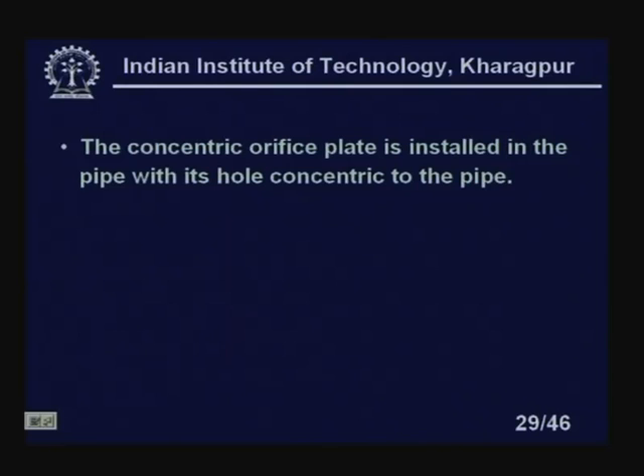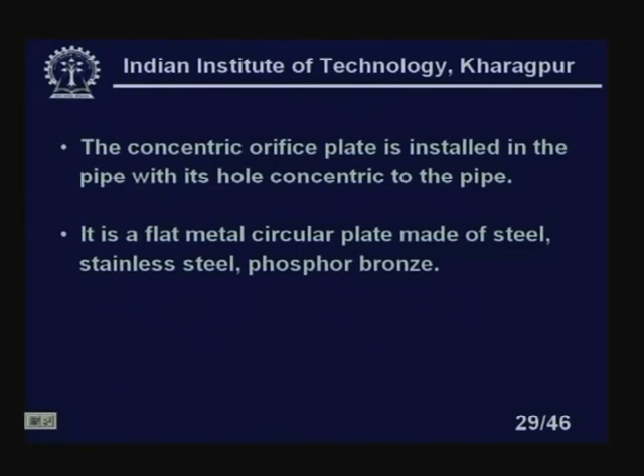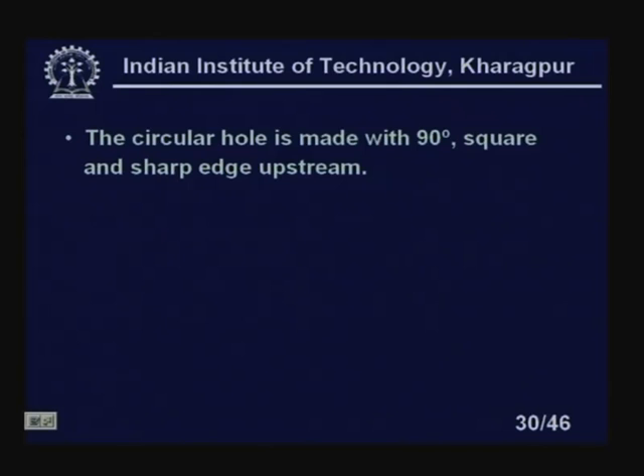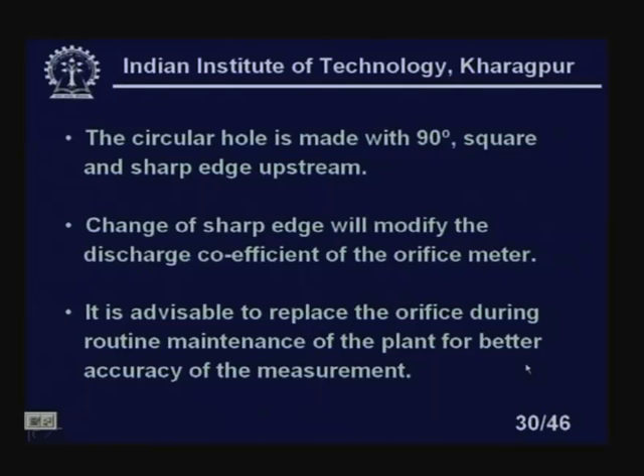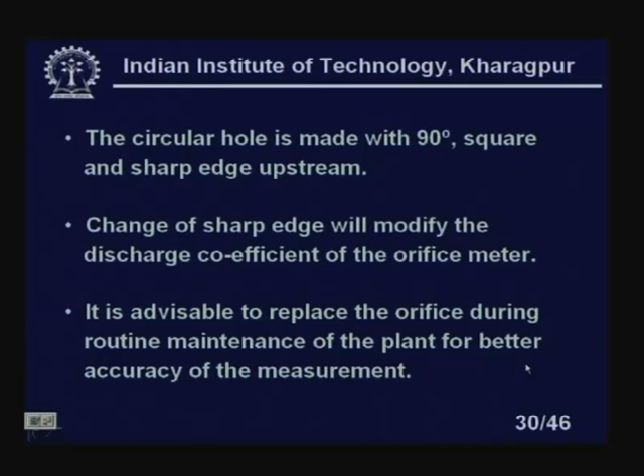The concentric orifice plate is installed with its hole concentric to the pipe. It is a flat metal circular plate made of steel, stainless steel, or phosphor bronze. Its thickness is only sufficient to withstand the buckling forces caused by the differential pressure across the plate. A circular hole is made with a 90-degree square and sharp upstream edge. Changes to the sharp edge will modify the discharge coefficient, so the orifice should be replaced during routine maintenance.